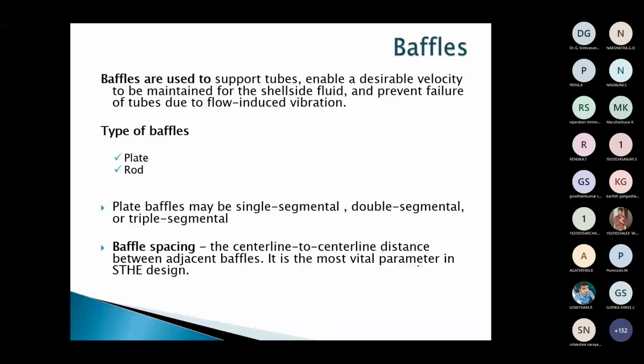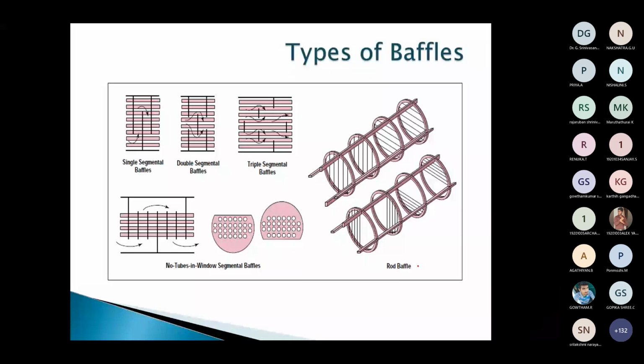Usually the baffle spacing is 1/5 to 1 times the inside diameter of the shell. We fix this based on the shell side diameter, either 1 times or the shell diameter divided by 5. So this is how the baffle spacing is fixed. There are two types of baffles: one is plate type, another one is rod type. You can see the two types here; this is rod type and this is plate type.